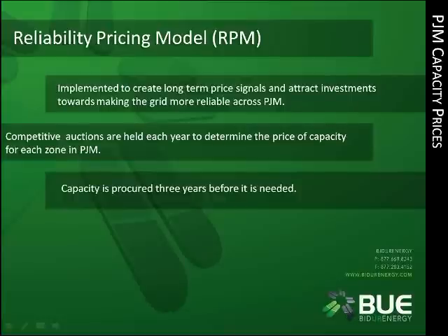This model is also very interesting when third-party suppliers are quoting their supply rates, because they have to take these capacity rates and your capacity obligation into account when quoting a rate. And in PJM, these rates are set in stone for the next 3 years. That capacity obligation has to be multiplied by the rate of the zone you're in, this RPM rate, to calculate what they call your capacity cost. And you will hear suppliers often call this a cap tag from time to time.